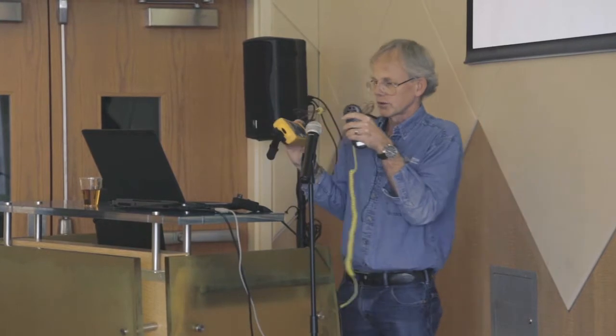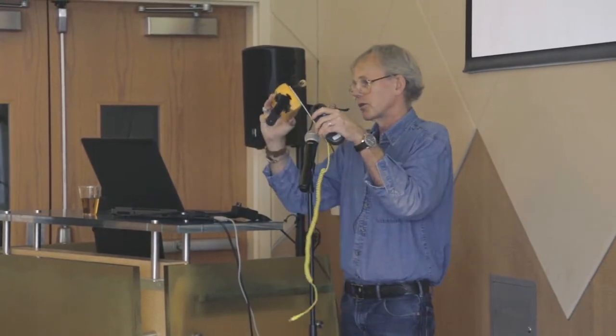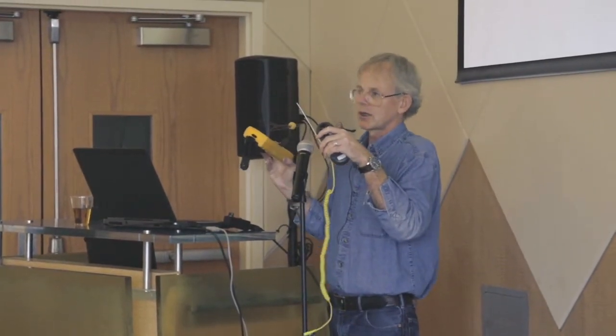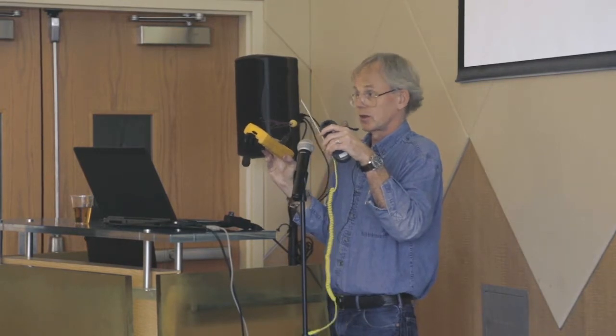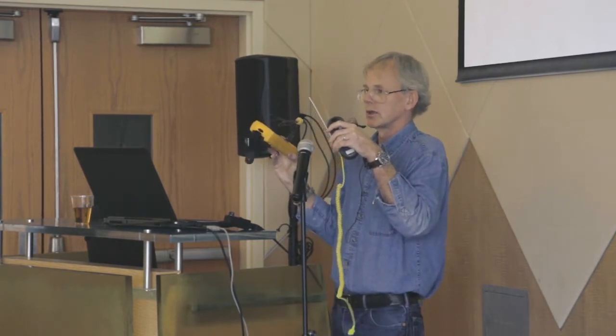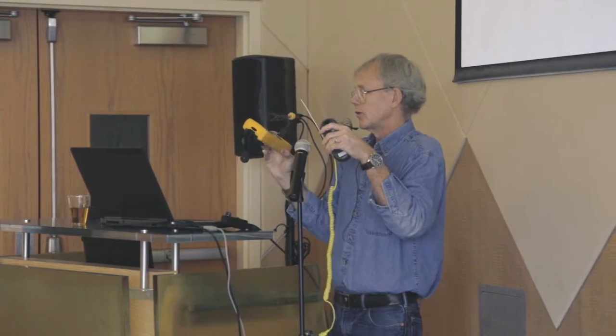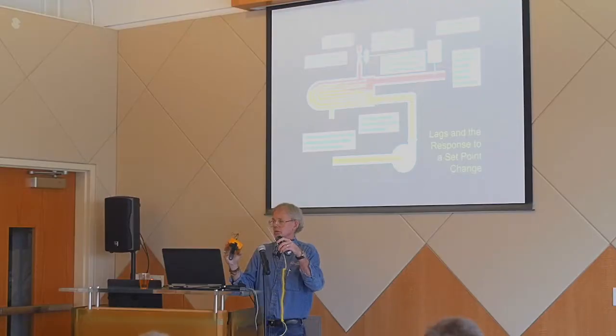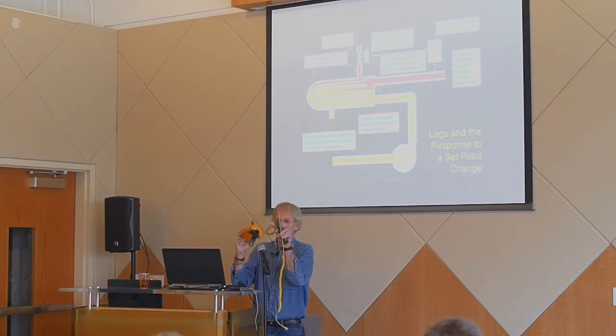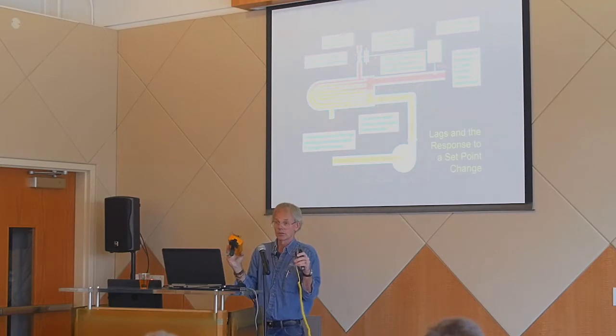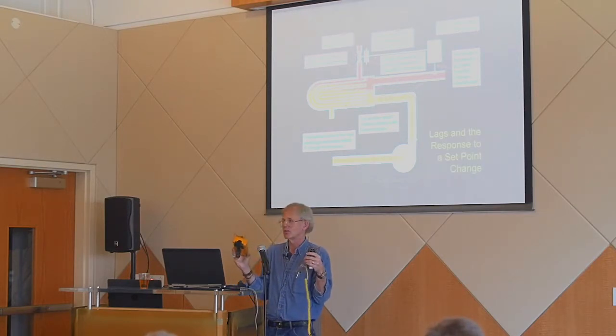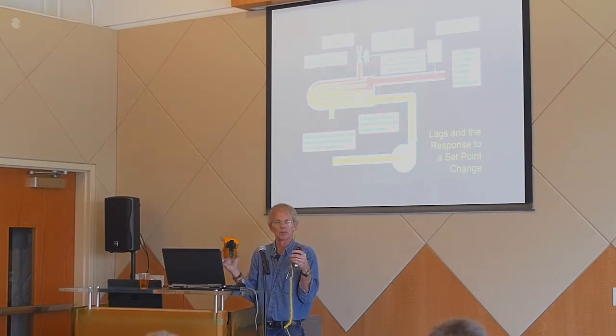So these little sensors, little brown wires or the silver thing, they're all type K thermocouples, same accuracy class. They're identical thermocouples from an accuracy class standpoint. But if you look close at them, they really aren't identical. Like this one's in a sheath. This one is that little sintered bead, but that bead is bigger than this bead. So what does the size of the bead and the sheath mean? What about that? How's that going to impact my ability to measure things? Lag. It's a thermal lag.